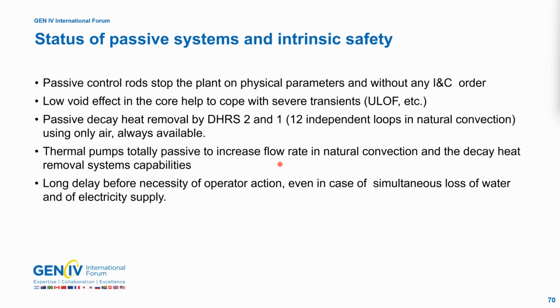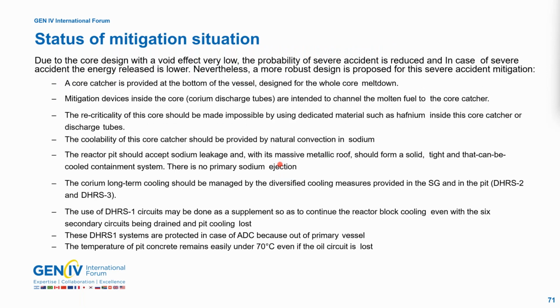We have passive decay heat removal by the DHRS2 and DHRS1, 12 independent loops that operate in natural convection, using only air, always available. We have seen the thermal pumps, totally passive, to increase the flow rate for the natural convection. And the result of that is you always have a long delay before necessity of operator reaction, even in case of simultaneous loss of water and electricity supply, as in Fukushima. And with an accident like Fukushima, on the SFR Smart, we have almost nothing to do. We have only to open the traps to install the natural convection.